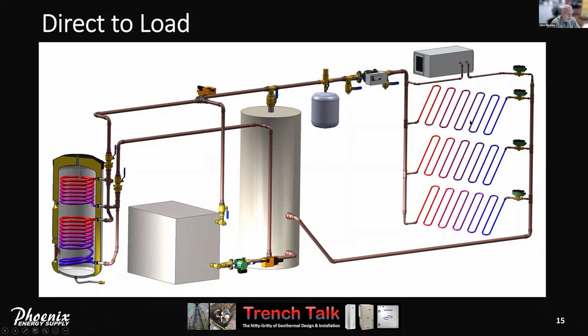We also like to see what we call demand enabled. If there is no zone calling, we might as well disable the heat pump, because we really don't know how long it's going to last. You can get in the middle of a nice sunny day for hours and not have a call. And there's no point in maintaining the buffer tank at some temperature when there is no need for heat.